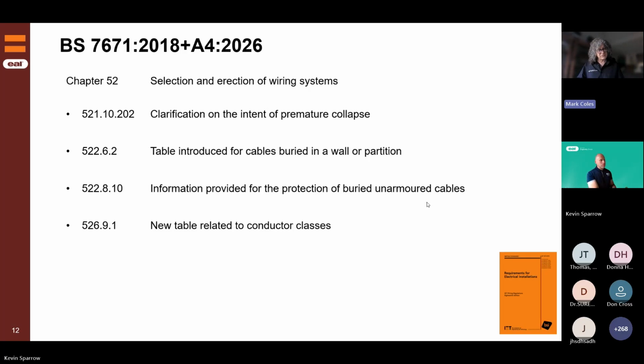Then 526.9.1, classification of conductors. This separates out the type of conductor, whether it's solid, stranded, fine wires, and defines the difference between rigid and flexible. If you look at that table, you'll see classes 3 and 4 are not included, because they were in the previous standard, BS EN 60228, and classes 3 and 4 have been superseded by what's now in class 2 and class 5. So it's not a mistake that classes 3 and 4 are missing.